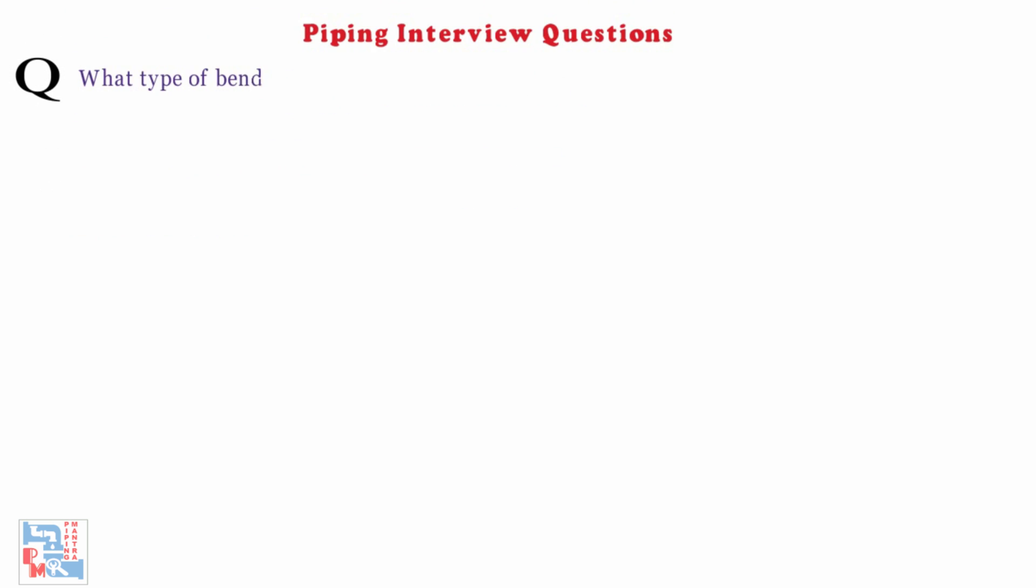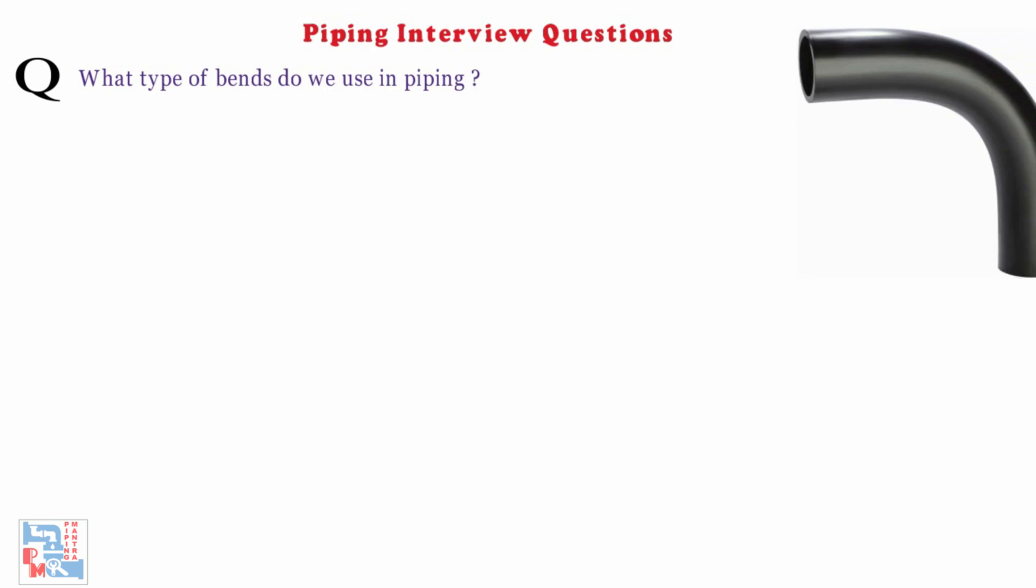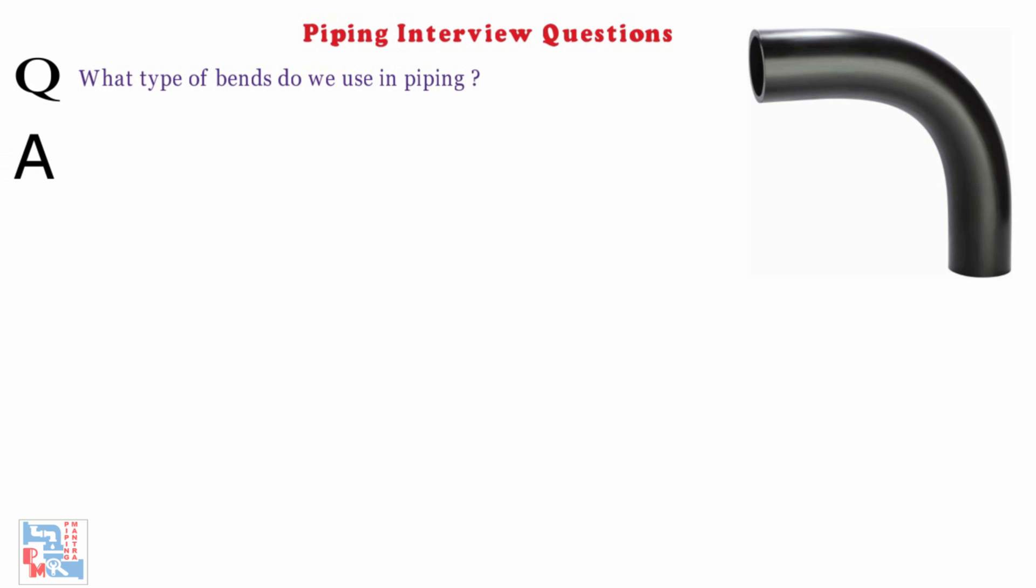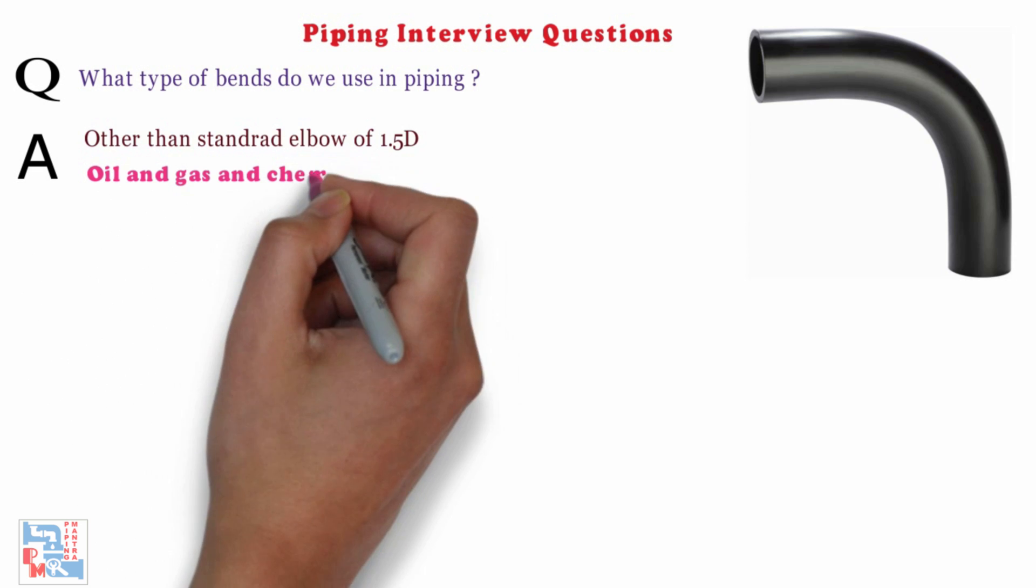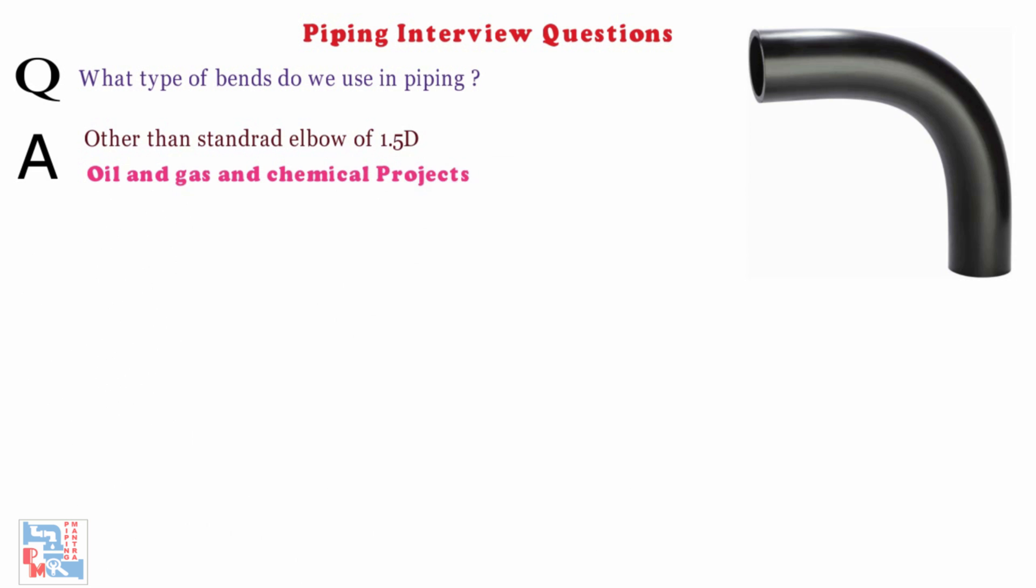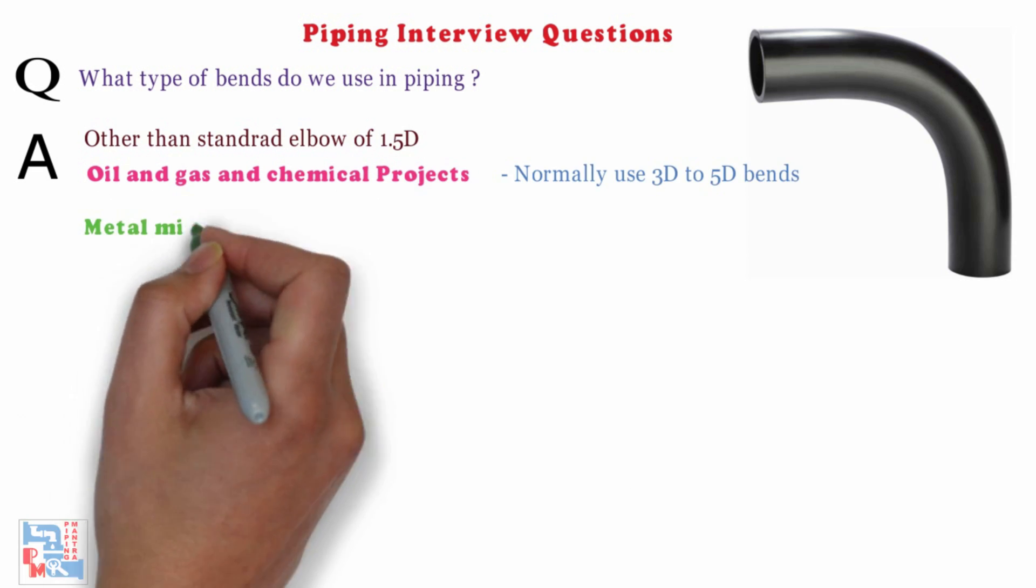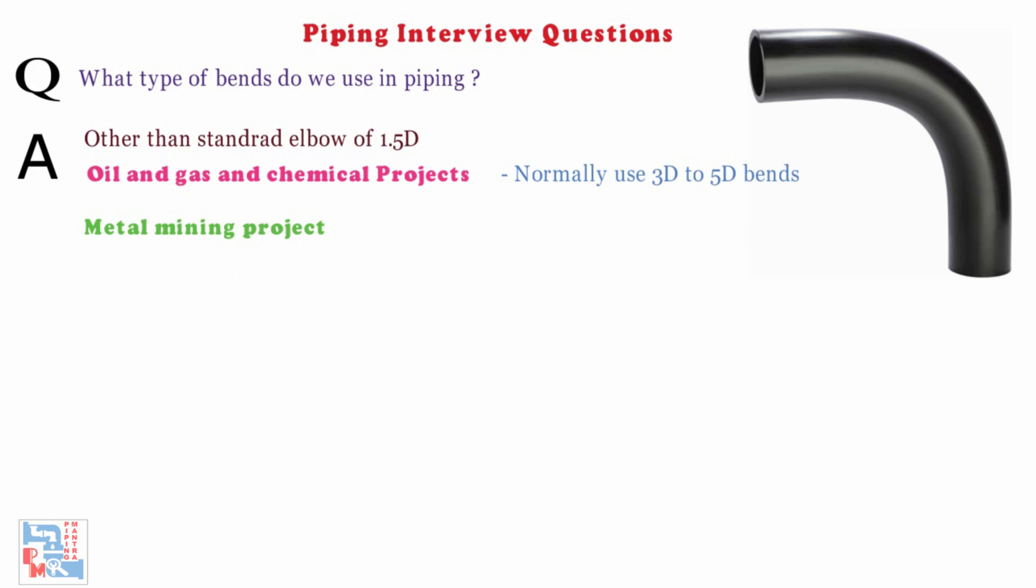Next, what type of bends do we use in piping? Other than standard elbows of 1.5D in oil and gas and chemical projects, we normally use 3D to 5D bends whereas in metal mining project we use 5D to 15D bends in slurry services. You can refer to our another video on fittings for more details on bends.